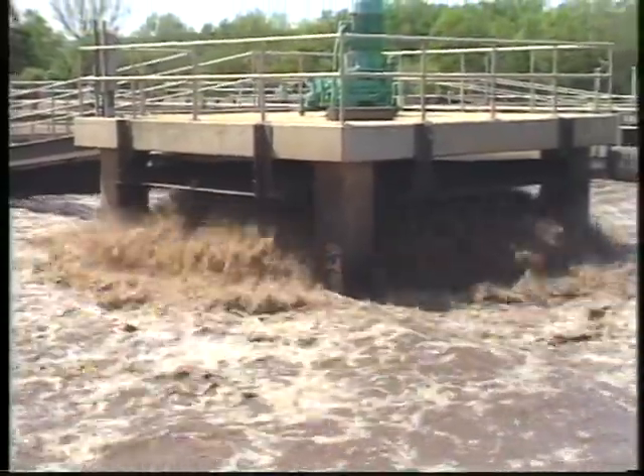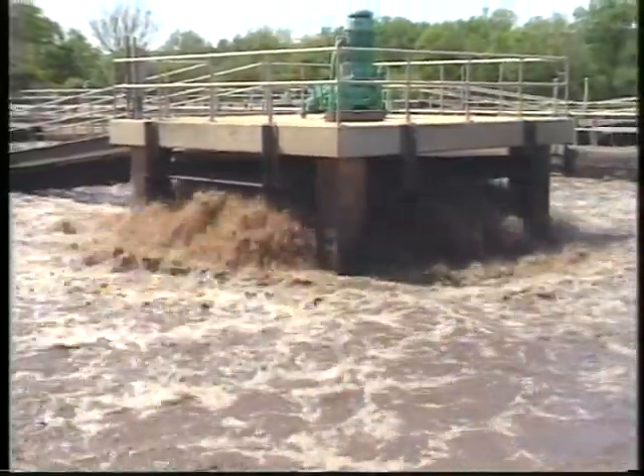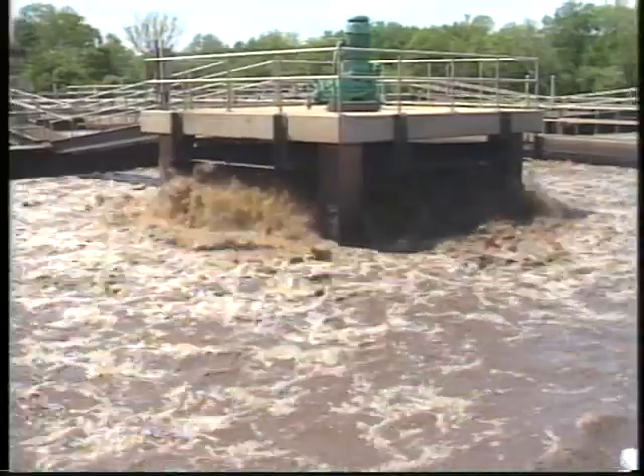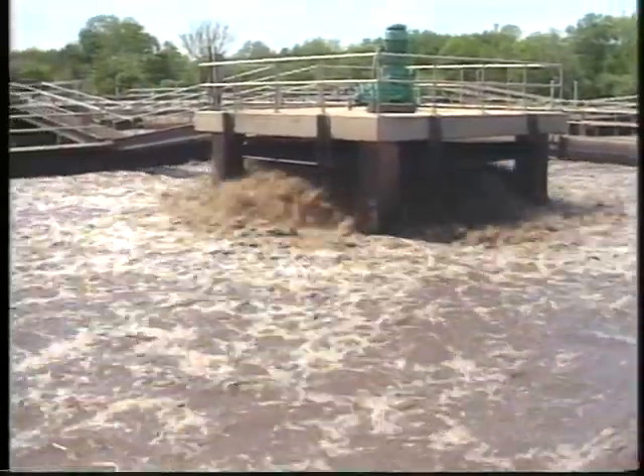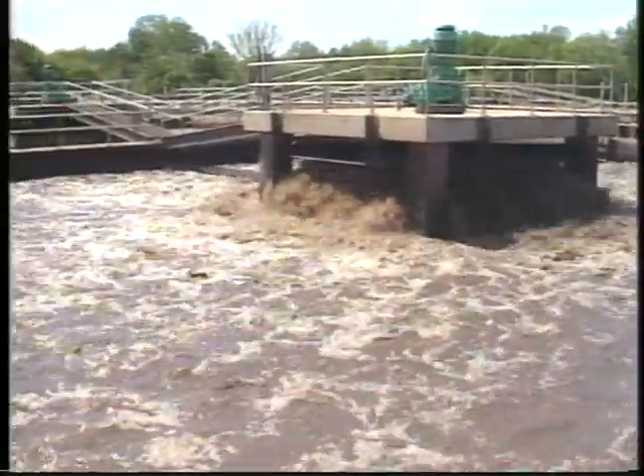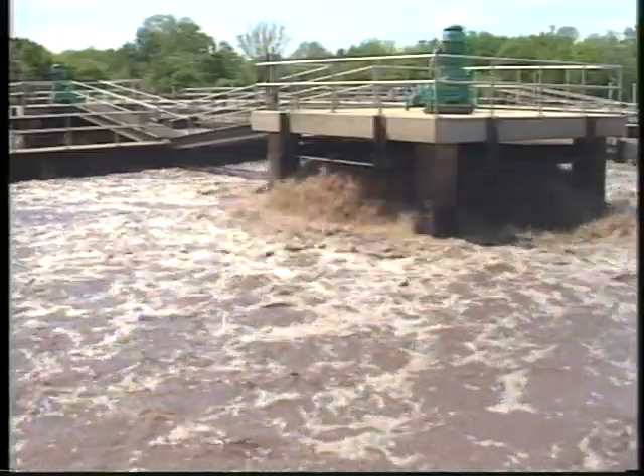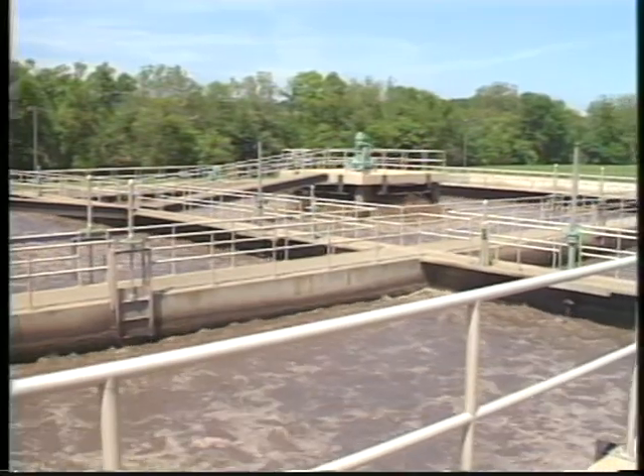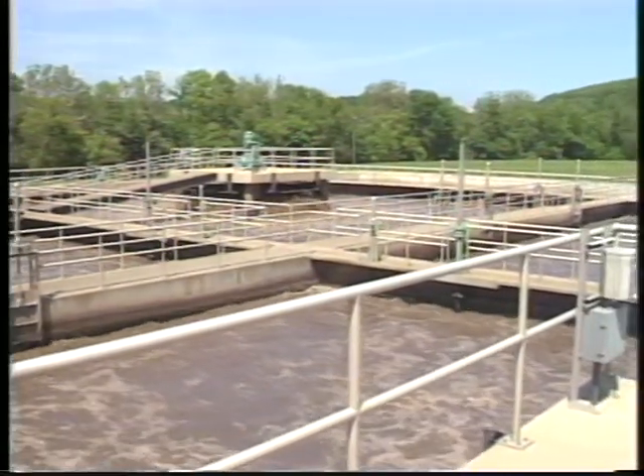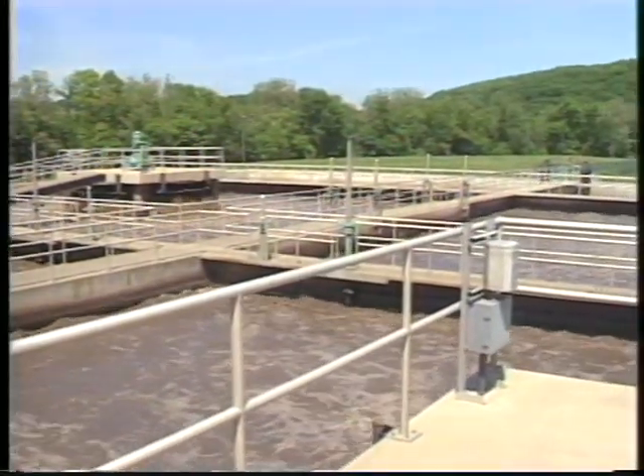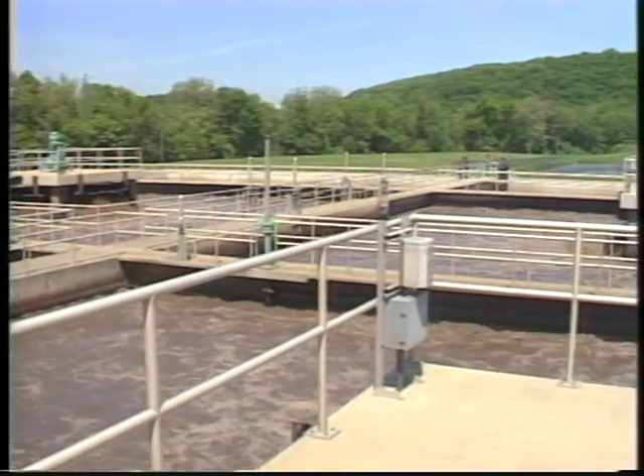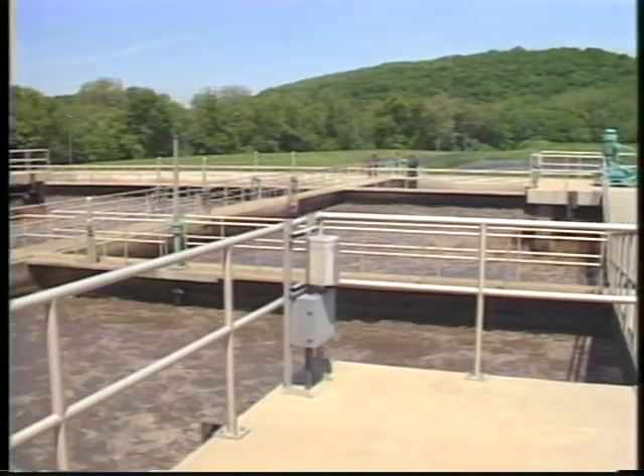Loadings and detention times for step feed are similar to conventional activated sludge. If you divert all the influent wastewater and return activated sludge to the inlet of the aeration tank, you will be operating in a conventional activated sludge mode. If you divert the return activated sludge to the tank inlet and the influent towards the latter two-thirds of the aeration tank, you are operating in the contact stabilization mode.